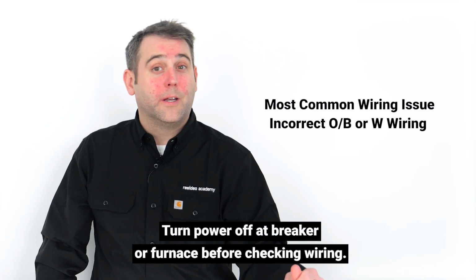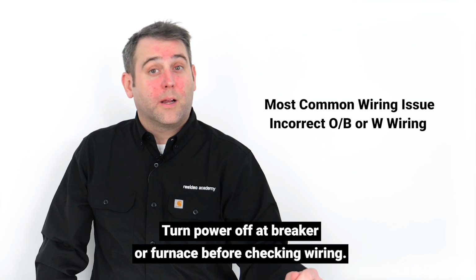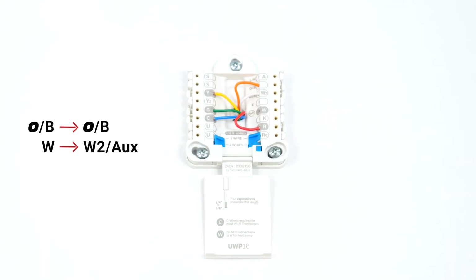The most common wiring issues are caused by incorrect wiring of the O/B or W wires. If your previous thermostat had separate O, B, O/B, and W wires, insert the O/B wire into the O/B terminal, and insert the W wire into the W2 or Aux terminal.